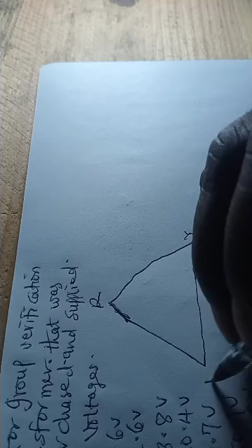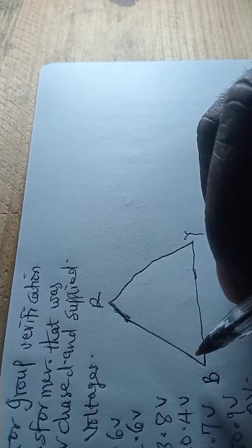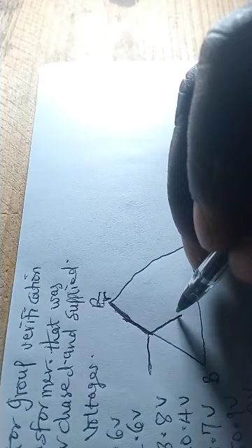So here now I have red, yellow, and blue. Since the transformer is Dyn1, it will be around here — if you check our 4 cardinal points, 1 o'clock will be around here. So I'm having it like this. It means small letter red will be here, yellow, and blue, and our neutral will be around here, star point N.